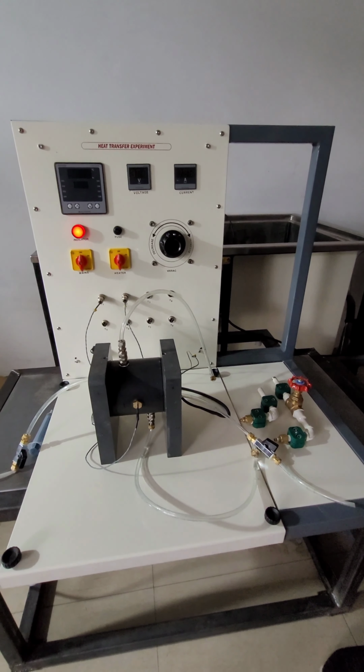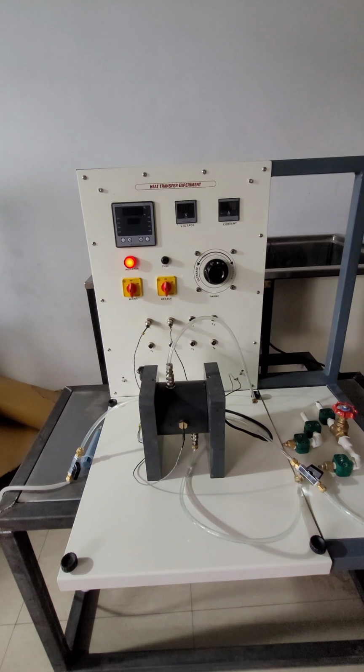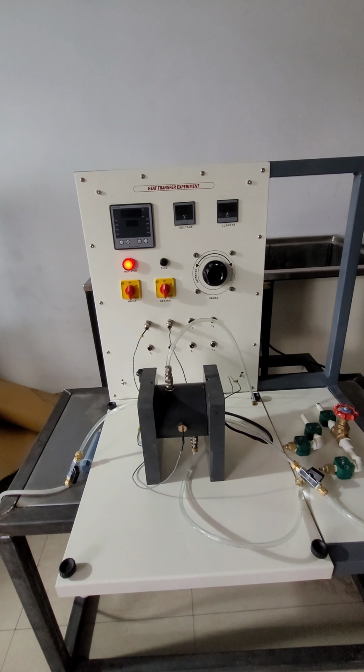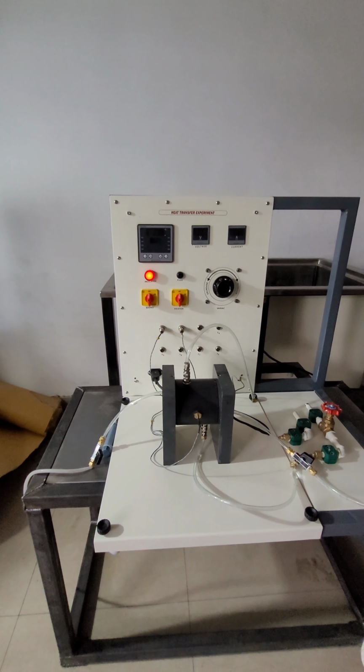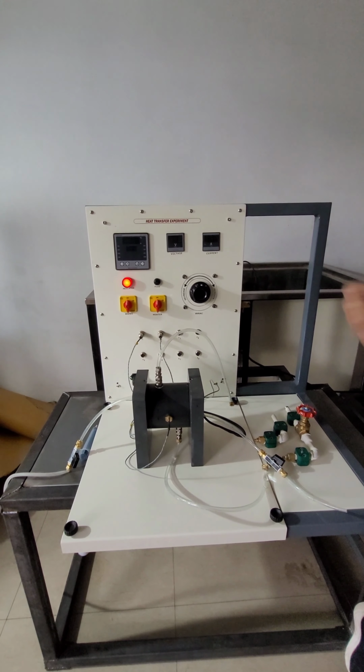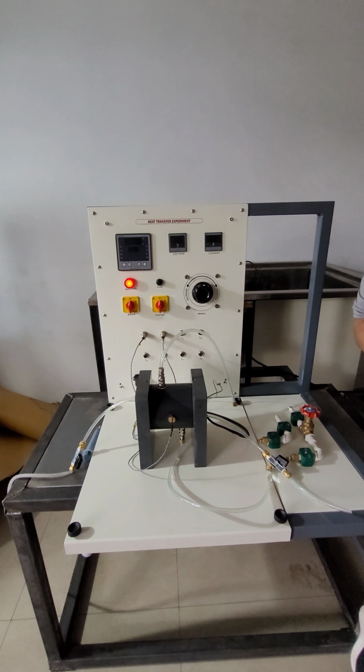Above this heating cylinder of 39.6 mm, there is another cylinder which has an ID of 40 mm. So you can see the inner cylinder has an OD of 39.6 mm, and the outer cylinder has an ID of 40 mm. So an annular gap of 0.4 mm is maintained with the help of O-rings installed at the outer edge of the heating rod.